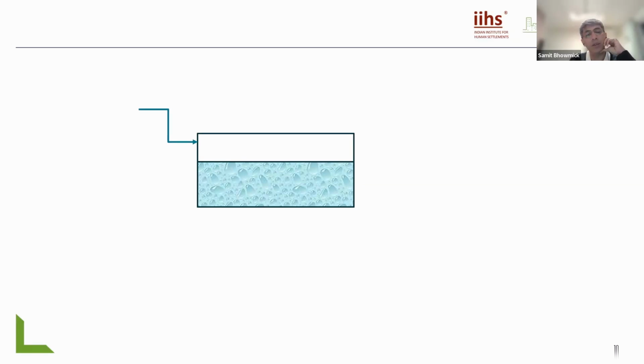So it is essential to make sure that the buildings are slightly positive. Infiltration is something which we have not looked at all. But because the extraction and pressure is not always matched, we have infiltration uncontrolled in most office buildings. But something which I always emphasize that should be checked: you can have different differential pressure sensors in a space to check how the space is behaving with respect to the ambient.